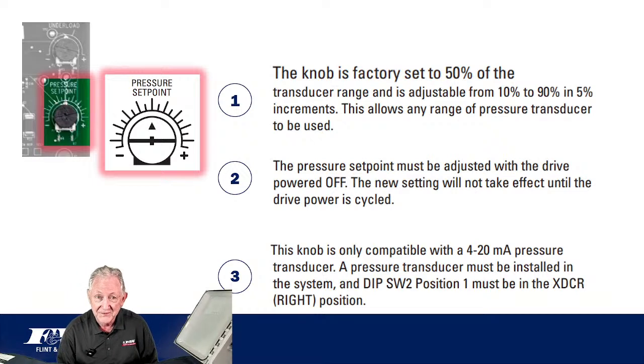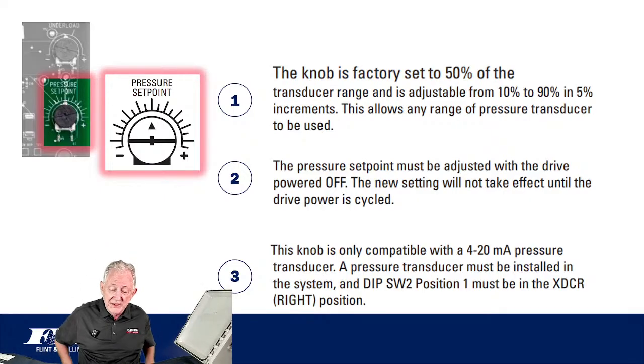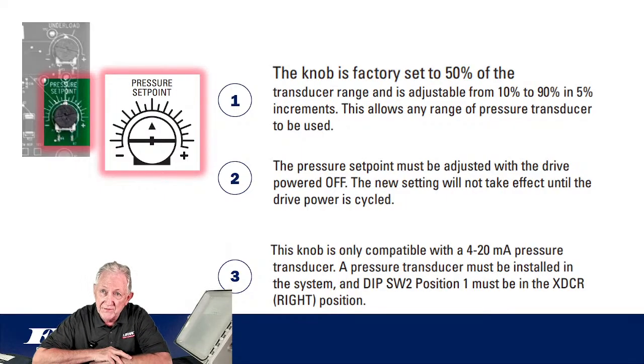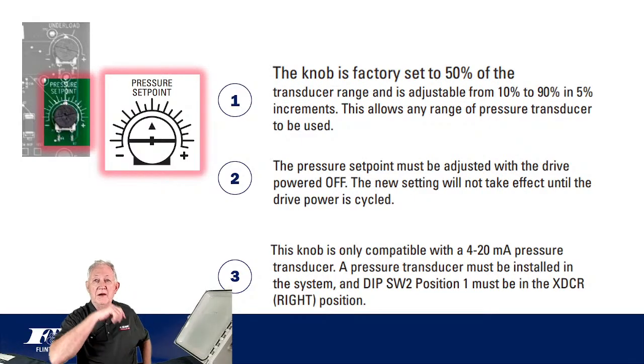Now that's, again, for a 100-pound transducer. If you have an application where you're using a 150 or a 200 or a 300-pound transducer, this same logic applies. However, those numbers are going to change because 50% of 150 is 75, right? So keep that in mind. The pressure set point must be adjusted when the drive is powered off, and then that new setting will take effect once you power it back up again.